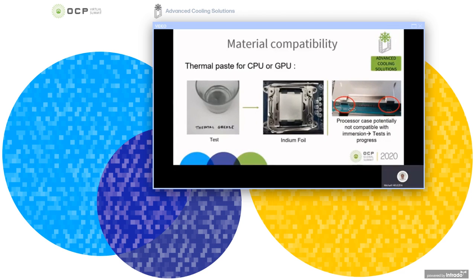For immersion cooling, a dielectric liquid is used. These liquids have specific chemical compatibilities. Obviously, the thermal paste used for air cooling are not compatible with these liquids. The thermal paste will gradually dissolve into the liquid, which may affect the cooling of the CPU or GPU. After several tests, we finally decided to replace these pastes by indium foil, stable in immersion.